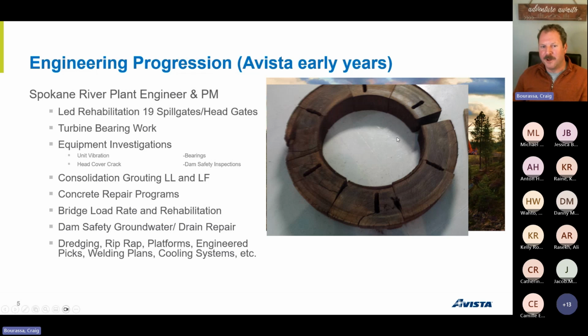We had one critical mistake on this project. We were painting the inside of the penstock during a 2 month outage, and these bearings, the wood, needs to stay wet, but we forgot to leave the water on it. It dried up the bearing, became very brittle, and basically disintegrated once we started running again. My job was to go in, identify what was going on, figure out why we were having thrust problems, and we replaced it with composite material.